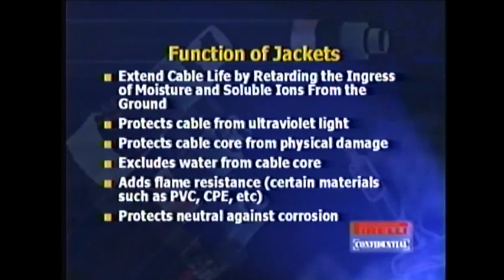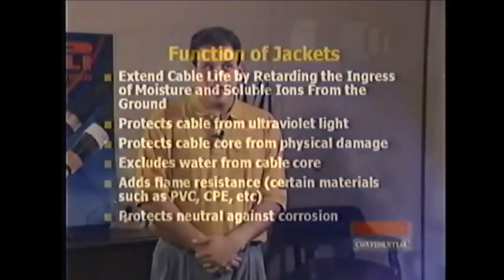Another function of a jacket would be to protect the cable from ultraviolet light. If you have the cables exposed to direct sunlight, you don't want those insulation shield materials exposed to that, because it can cause damage. So you put a jacket on there to keep the sun from directly hitting the cable. You can also, of course, protect the cable core from physical damage during mechanical pulls. Jackets can also exclude water from the cable core. Of course, water-soluble agents beneath the jacket aid in this much more, but standard jackets, such as linear low-density polyethylene, which have basically a low moisture vapor transmission rate, can do a very good job in keeping water out of the core.